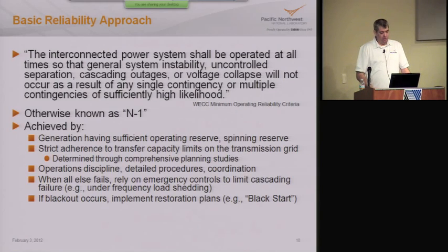Shedding firm load, then, is a situation where either unintentionally, like a blackout, or when all else fails, an operator can see that they can save the system by, say, turning off a city. But that's interrupting every customer in that area, and nobody's signed up for that. So that's pretty much a bad day when that happens.